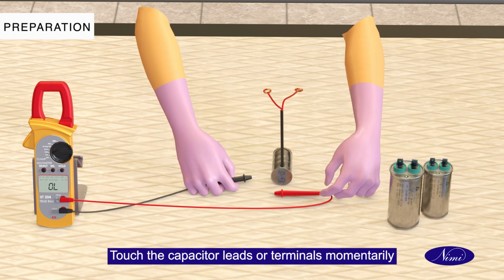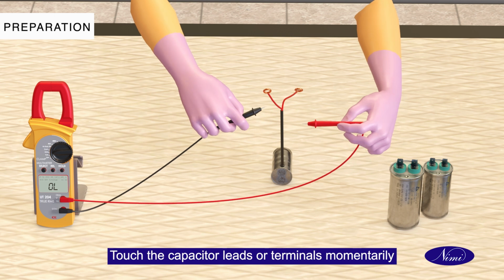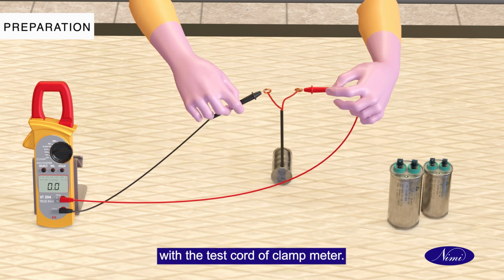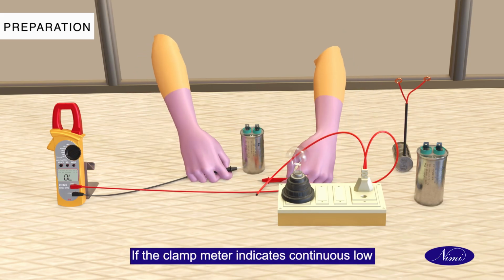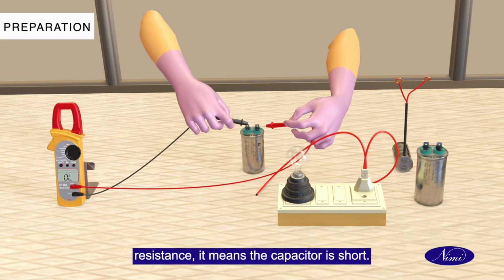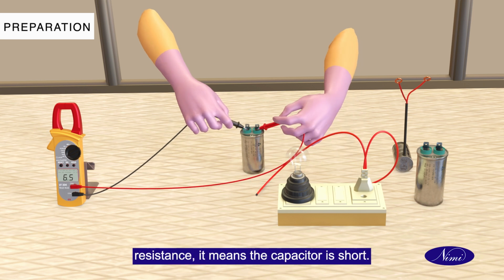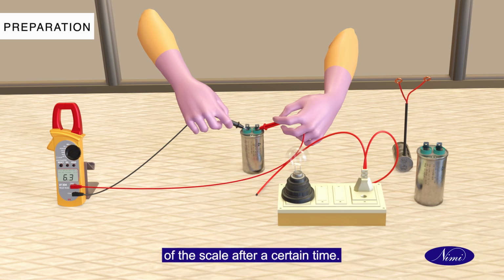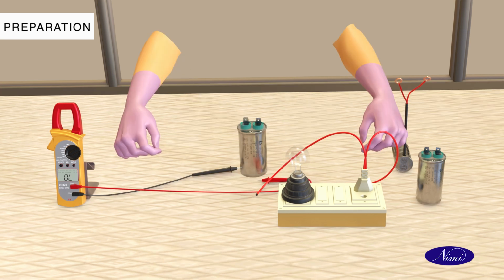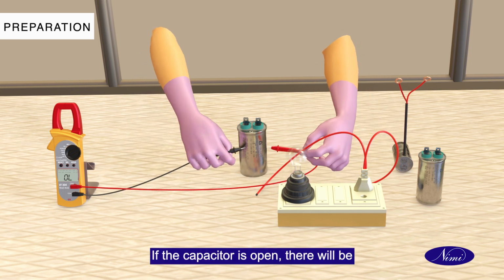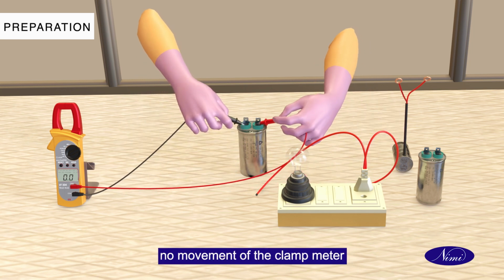Touch the capacitor lead or terminals momentarily with the test cord of the clamp meter. Watch for a slight instantaneous deflection of the clamp meter, indicating a satisfactory capacitor. If the clamp meter indicates continuous low resistance, it means the capacitor is short. The clamp meter will move back to the infinity end of the scale after a certain time. If the capacitor is open, there will be no movement of the clamp meter.